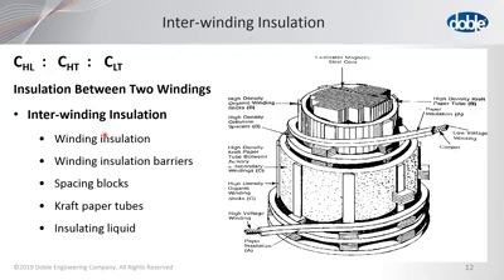Next. Okay. What happens if we have a buried tertiary? A buried tertiary means that no bushings are brought out of the transformer for connection. In that case, it would be tested as a two-winding transformer. You have to have the ability to connect to the winding for it to be a viable test point, right? So a 3-winding transformer with only bushings from the low and the high voltage could only be tested as a 2-winding transformer.